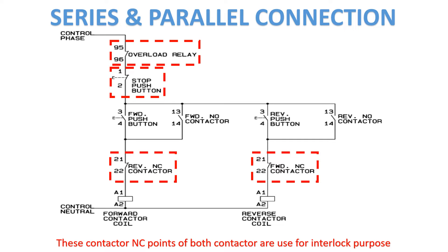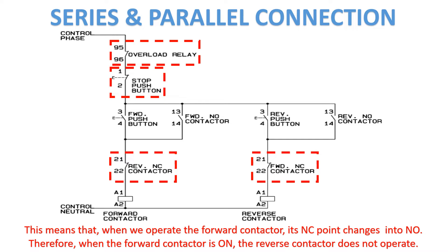These contactor NC points are used for interlock purpose. This means that when we operate the forward contactor, its NC point changes into NO. Therefore, when the forward contactor is on, the reverse contactor does not operate.